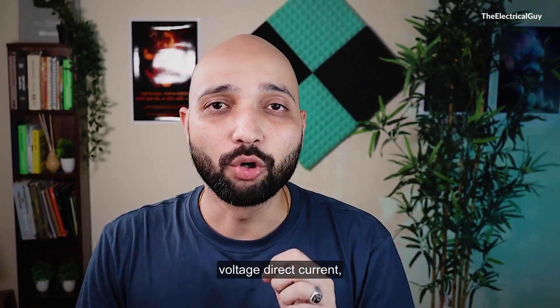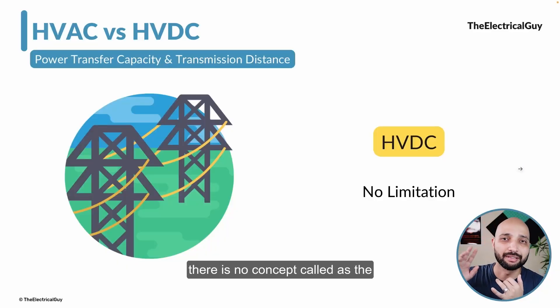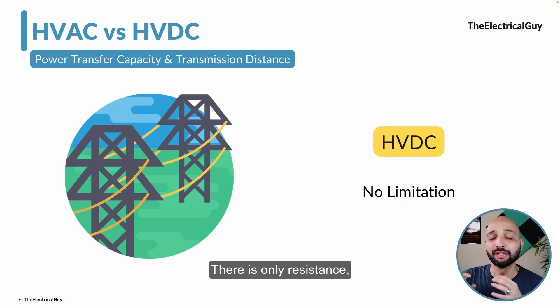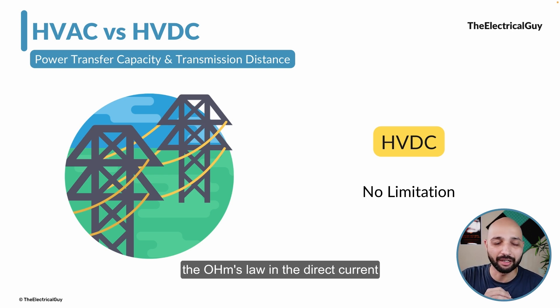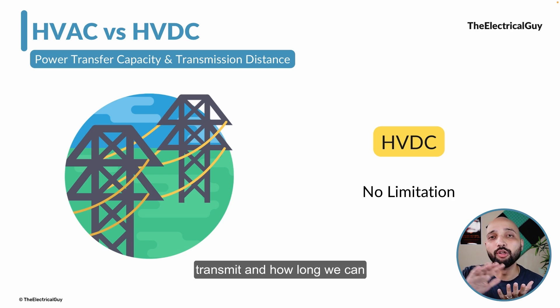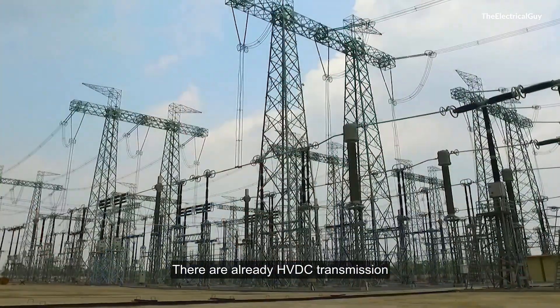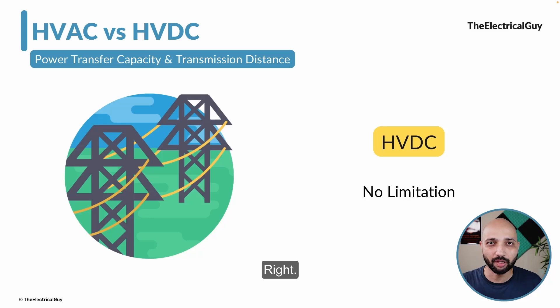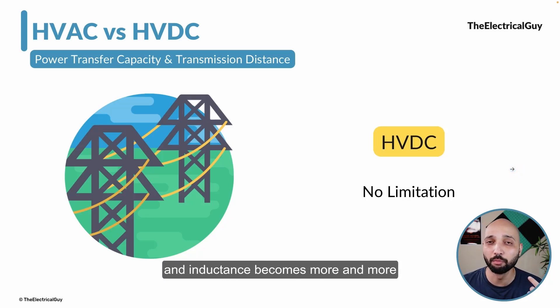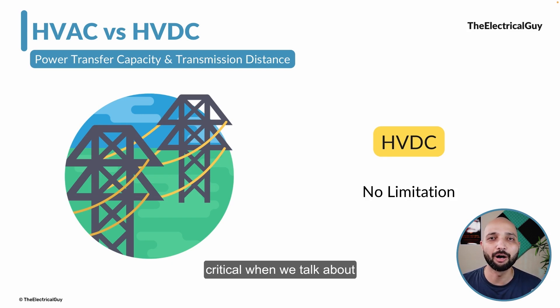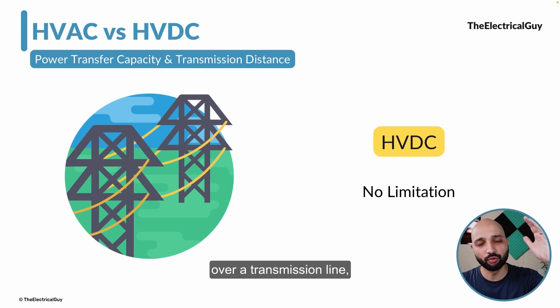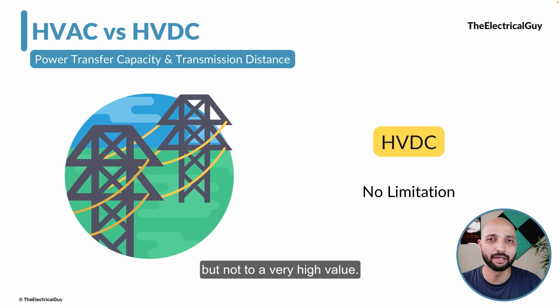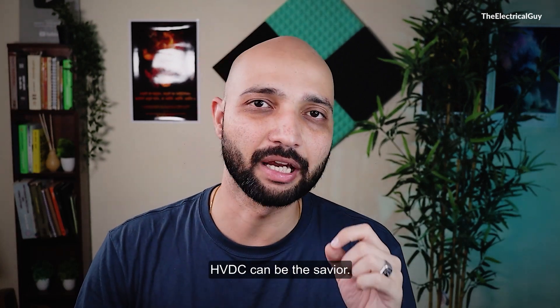When we talk about high voltage direct current, there is no concept of capacitance or inductance in HVDC — only resistance, governed by Ohm's law. Technically there is no limitation on how much power we can transmit or how far. There are already HVDC transmission lines transmitting power over 1000–2000 km without any issue. This problem of capacitance and inductance becomes even more critical in cables compared to overhead transmission lines, and in that case HVDC can be the savior.